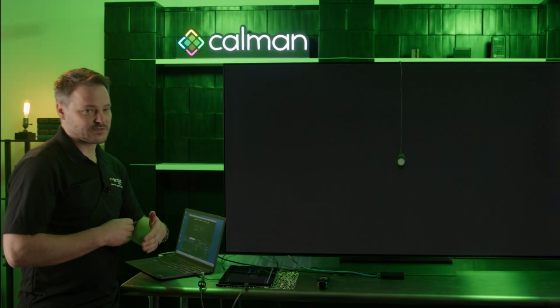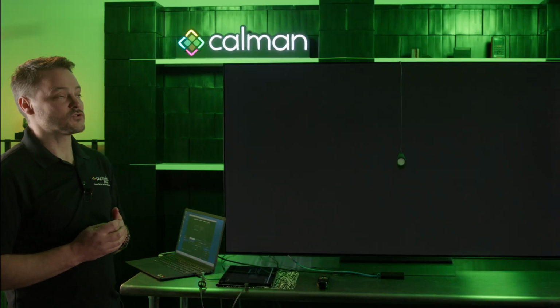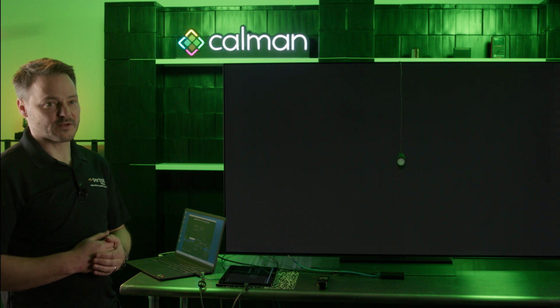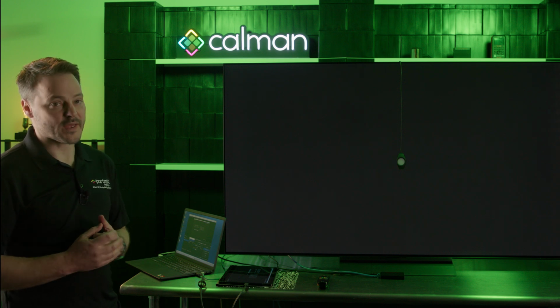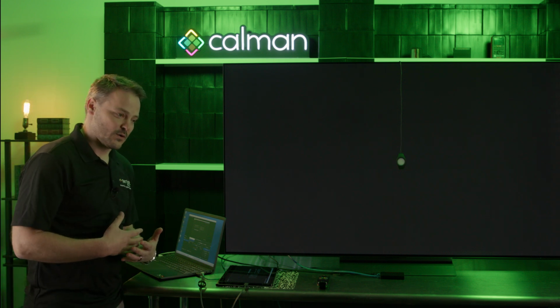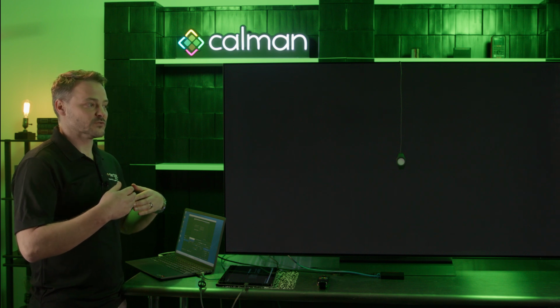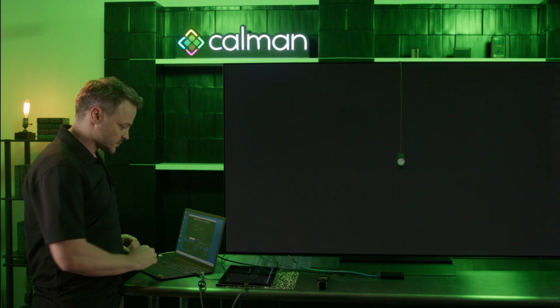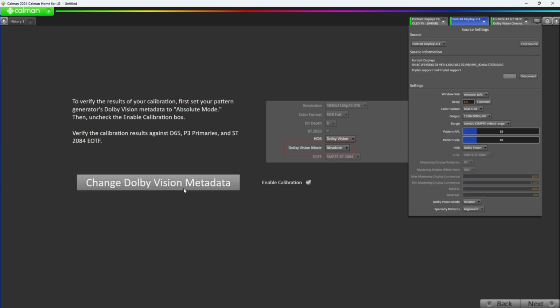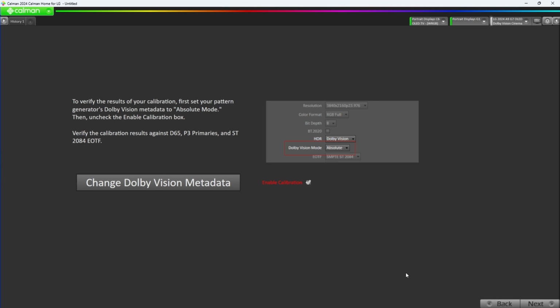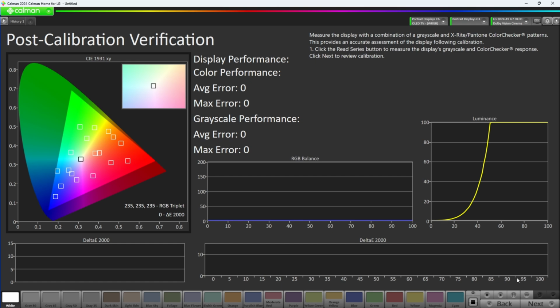And now, just like when we were going into the calibration, we do need to make sure that after the calibration, we switch our metadata for the Dolby Vision and disable the cal start. Those are two things that are going to allow us to measure the display in Dolby Vision as it would actually be watched. You can press the change Dolby Vision metadata, or you can just open the source tab and change the Dolby Vision mode from relative to absolute. Disable cal start. And then we're going to hit next, and we're going to do our post-calibration measurement.